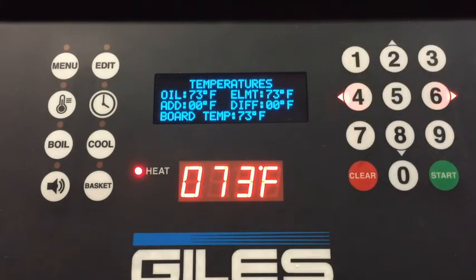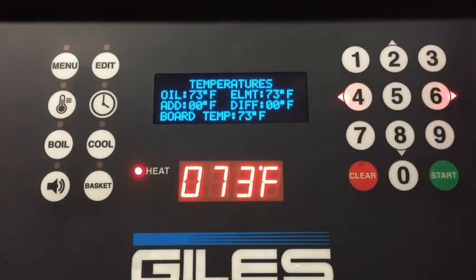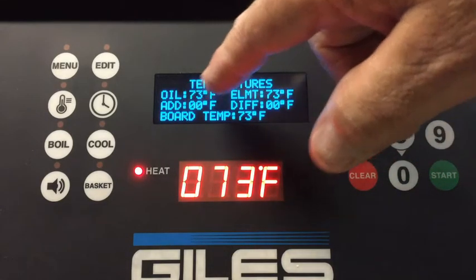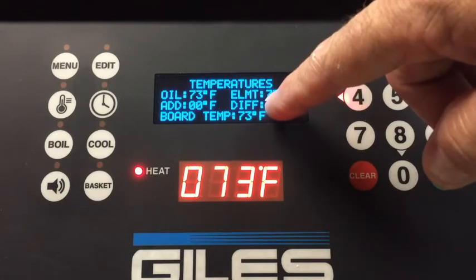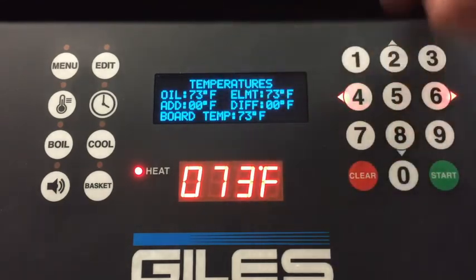And you can see the different temperature probes. Now, in an actual setting, those should all pretty much be the same. Again, this particular unit does not have an add level probe. If it did, with no oil in it, or with the temperature just sitting there, if everything has not been heated or anything, you can turn this on. And these should be relatively the same. You'll see the element right now is 73, the oil 73, the add is at 0, but it would be at 73 had it been in there.